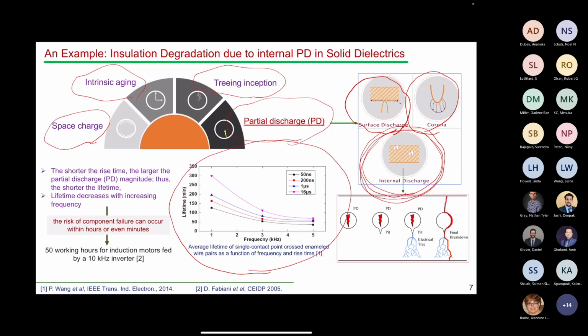As I increase the frequency, the lifetime decreases, and as the rise time gets shorter, the magnitude of the PD gets larger, giving you a shorter lifetime. This greatly affects the lifetime of the insulation.